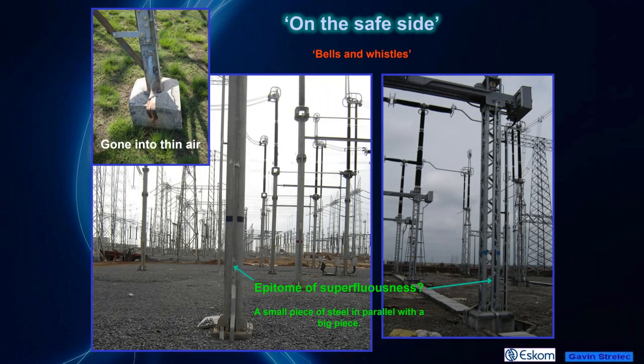These pictures come from applications of galvanized steel for earthing in India at 765 kV level substations. And we asked the question, this conductor that runs down a galvanized steel structure, is that really necessary? Galvanized steel can be used, but it has serious drawbacks, one of them being corrosion. On the left-hand side, we see how these conductors can just disappear into thin air if we do not take care of the corrosion protection.